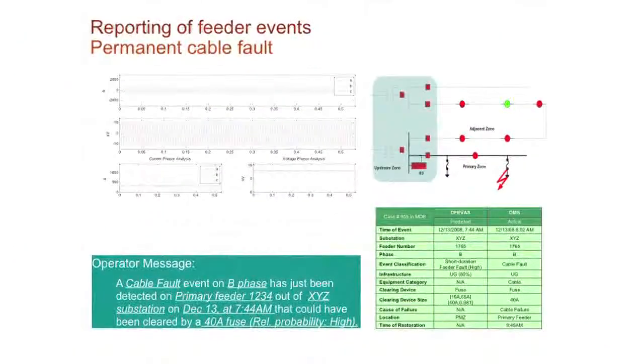Now with this kind of operation, back to that picture again - the primary zone, the adjacent zone. I've got my Ref 615 at the head with my station computer. I have a fault in the lateral fuse. I can give a message that says a cable fault event on phase B has just been detected on the primary feeder, 1765 in this case, at this date, at this time, cleared by a 40 amp fuse. We even go as far as giving a reliability rating - how confident are we about this report conclusion?